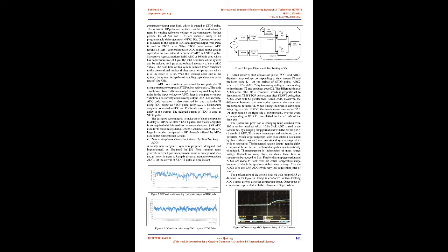Successive approximation, SAR, ADC of 16-bit is used which has conversion time of 1 µs. The total dead time of the system can be reduced to 1 µs using onboard memory to store ADC values. The dead time of the system is much lower compared to the conventional nuclear timing spectroscopy system which is of the order of 10 µs. With this reduced dead time, the system is capable of handling typical nuclear event rate of 100 kHz.